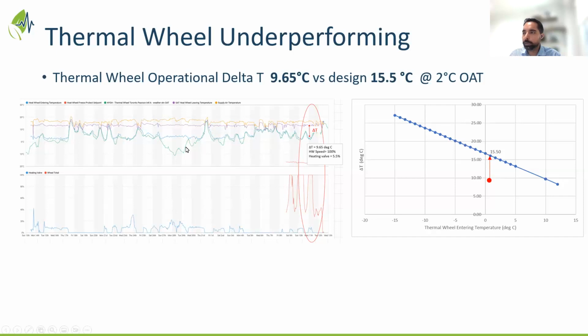The second most common factor that we've seen is the thermal wheel underperforming. If you look at the graph on the right-hand side of your screen, this is a graph of the thermal wheel entering air temperature versus the outside air temperature, or versus the delta T. If you look from right to left, as your entering wheel temperature increases or decreases. So if you follow the extreme example here, at -15 degrees C, your expected delta T per the design is around 26.5 degrees C. So you should see a supply air of around 11 degrees C coming out of the wheel if your entering air temperature on your wheel is -15.